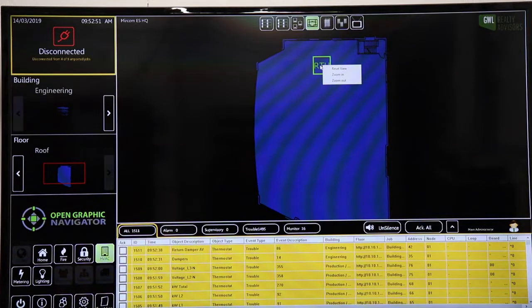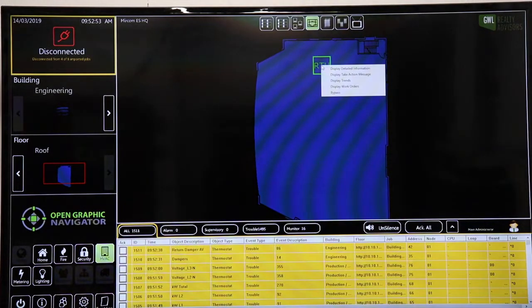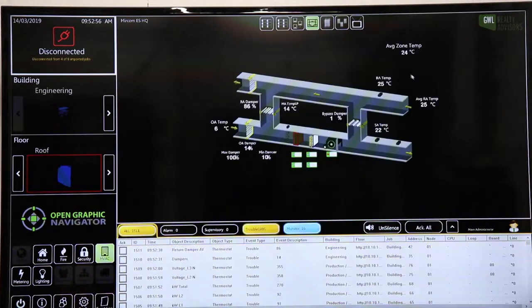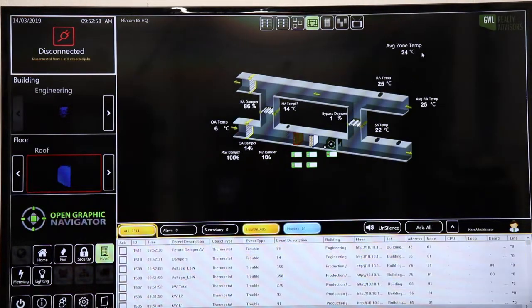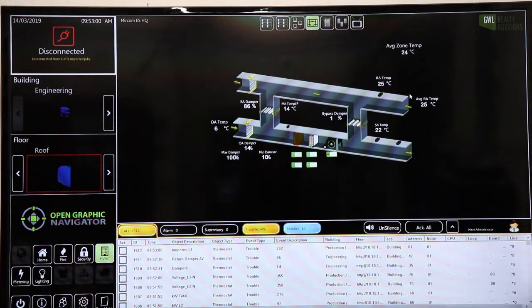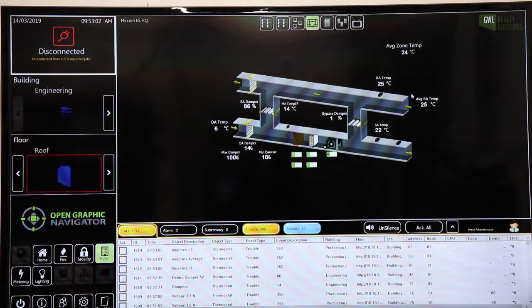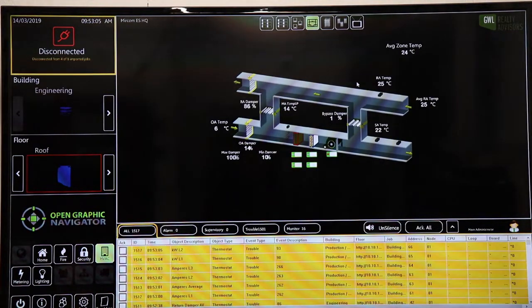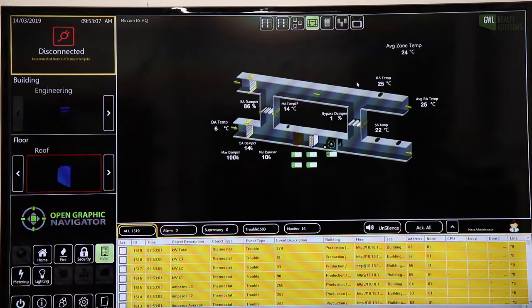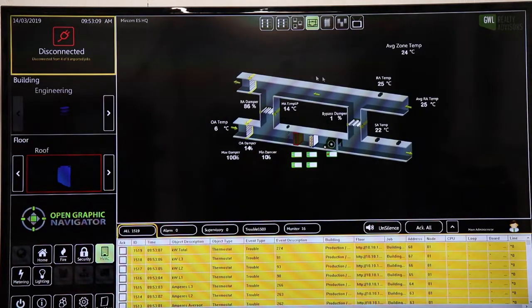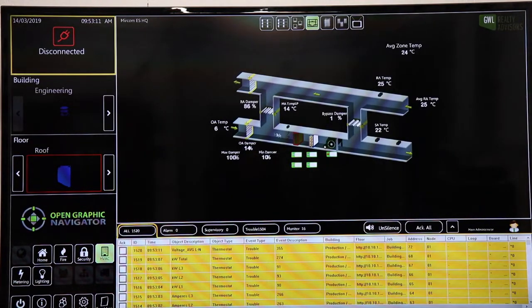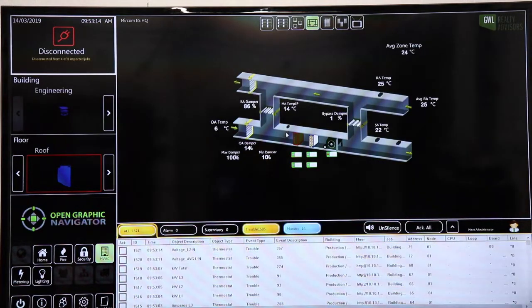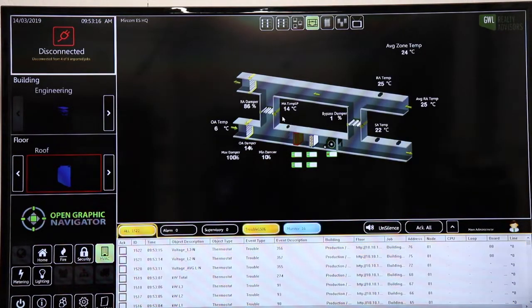If we want to find out more information about the real-time parameters in that rooftop unit, again, I simply right-click, get to my context menu, and look for the detailed information about this system. Here, we've used Modbus interface to pull in outside air temperature, fan damper positions, fan speeds, and other information pertinent to the HVAC control system. This allows the building operator to very quickly get a real-time view of what's happening on the mechanical control system.